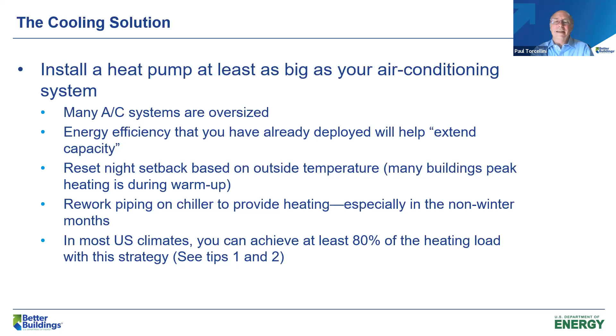Another option is reworking the plumbing on the chiller to also provide heating, especially in non-winter months. One strategy is using the heat coming off your chiller to provide reheat if you have a hydronic-based reheat system. Going back to tips 1 and 2, energy efficiency, in most US climates you can achieve at least 80% of the heating load with this kind of strategy. Next slide.